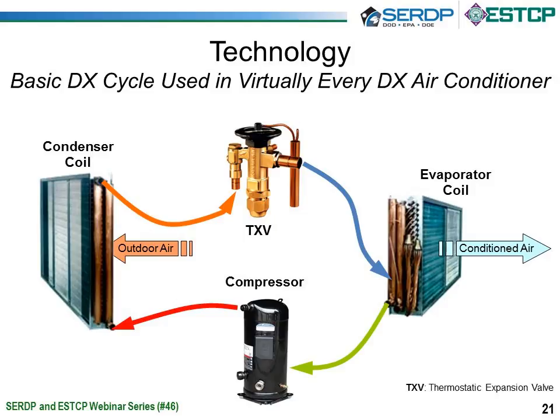From the condenser coil, the liquid goes to the thermostatic expansion valve. And this is really where the magic of refrigeration happens, where the liquid, which is high temperature, in a standard system it may be, say, 10 degrees above ambient. So if it's 90 out, it's probably around 100 degrees. And it is expanded to a low pressure mixture of vapor and liquid that's maybe at about 45 degrees.